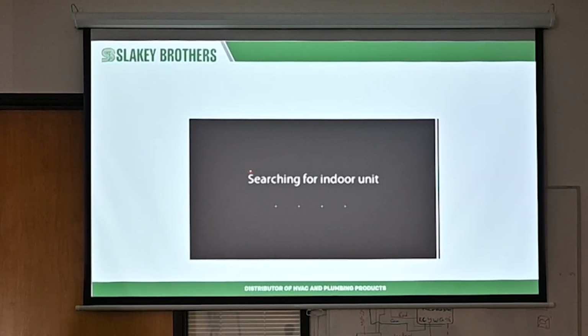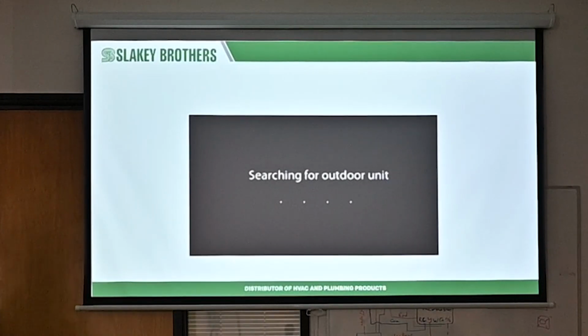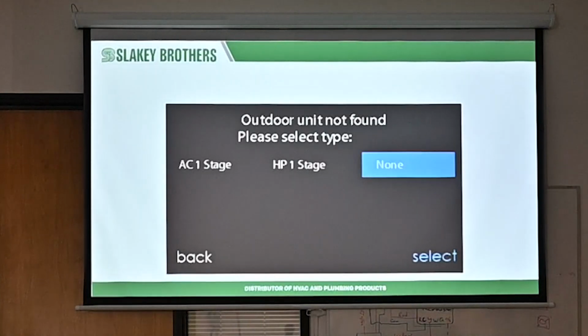And then go from there. Obviously, if we're here, it means that that indoor unit has power. But now there's something wrong with the communication signal between the Connex and the indoor unit. Now searching for outdoor unit. Okay, so again, this is a scenario if you're installing a Connex system or Evolution system with a non-Evolution outdoor unit, you're going to get this: outdoor unit not found. Please select type of what you have. You're going to tell it AC single stage, AC or heat pump 1 stage, or none.